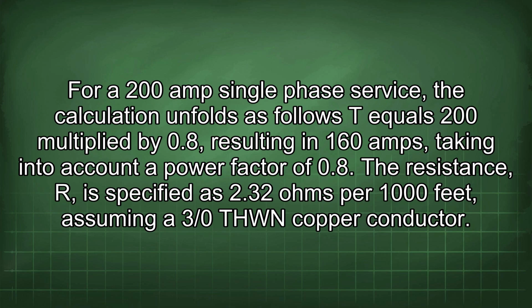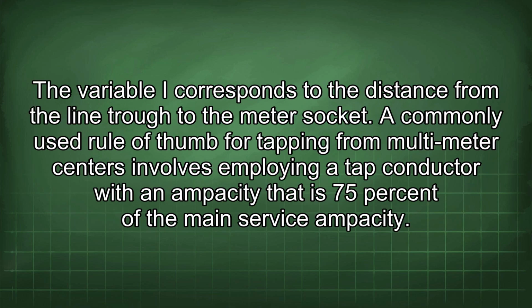For a 200 amp single-phase service, the calculation unfolds as follows: T equals 200 multiplied by 0.8, resulting in 160 amps, taking into account a power factor of 0.8. The resistance, R, is specified as 2.32 ohms per 1000 feet, assuming a 3/0 THWN copper conductor. The variable I corresponds to the distance from the line trough to the meter socket.